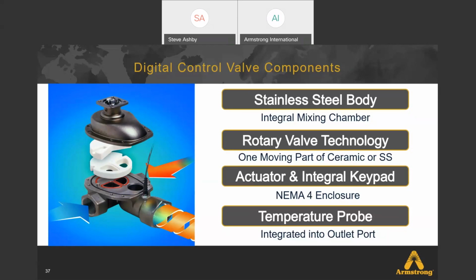This is a rotary valve, so the only thing that's moving in this valve is the top disc. You'll see the bottom disc secures in the valve body, and that top disc has a notch cut out of it. That's coupled to the spindle to the stepper motor in the actuator. So the only thing that moves in the valve is that top disc, and all that does is proportion your two water feeds to be at the precise ratio to maintain a set temperature.